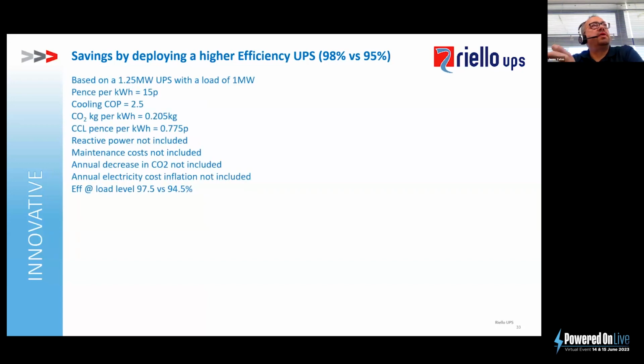If we deploy a UPS system, put a 98% UPS in place of a 95% UPS, don't get me wrong, that is a well-performing UPS system. Based on a 1.25 megawatt UPS with a 1 megawatt load, you can see 15 pence per kilowatt, cooling coefficient 2.5, CO2 0.2 kgs, climate control levy of 0.77. I have not included reactive power, maintenance costs, annual decrease in CO2, or any annual increase in electricity costs.